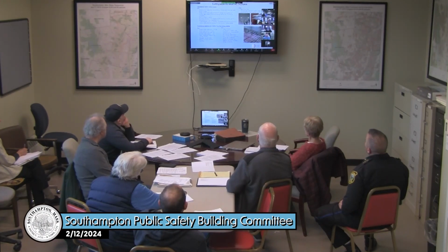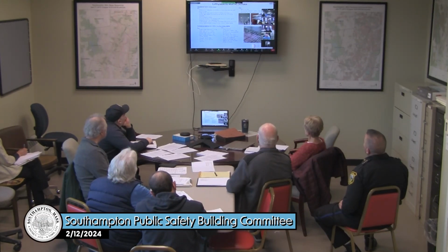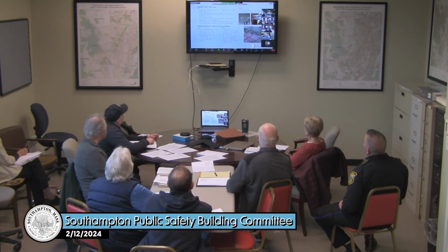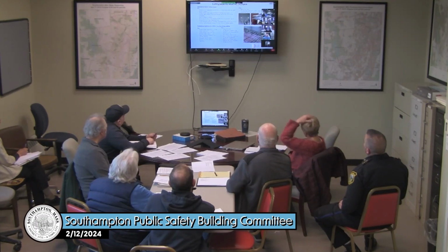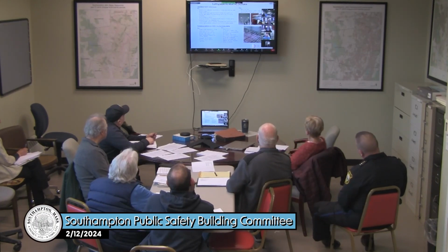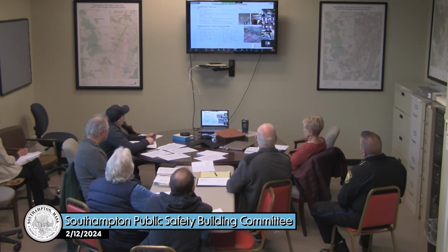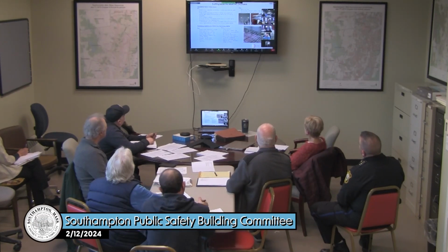Supplemental heating systems, for like your apparatus bay, depending on what system ultimately gets selected, will determine what we provide. If we're providing a hydronic-based system, we could provide a hot water radiant floor system. If we go with an all-electric approach, like an air source VRF system, there's no source of hot water, so we could provide an electric-based one, but that would really just be for backup, or on extremely cold days where the system isn't able to maintain the space temp. An electric-based radiant slab would be expensive to operate as your primary source, so it would really just be secondary.